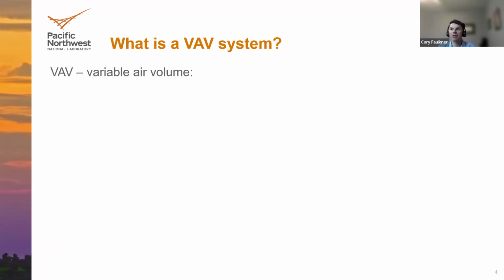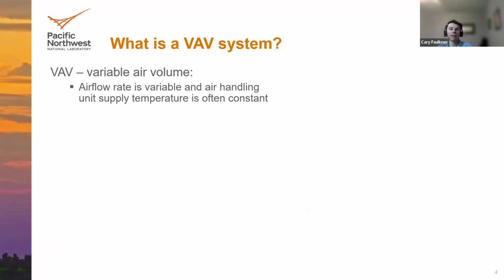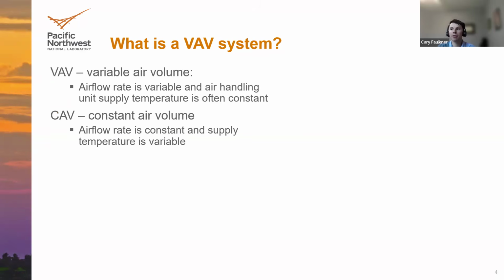Well, VAV stands for variable air volume. By this, it means that the airflow rate supplied by the HVAC system is variable, which I'll contrast to constant air volume systems. So typically the strategy is that the HVAC system can vary the airflow rate, and then perhaps the supply air temperature can be held constant from the air handling unit, and just the airflow rate can be varied to try and meet heating and cooling demands. So this contrasts with a constant air volume system where the airflow rate is held constant. It's maybe just an on-off single speed fan to supply air to the building, and then the supply air temperature might be variable to meet the heating or cooling loads.